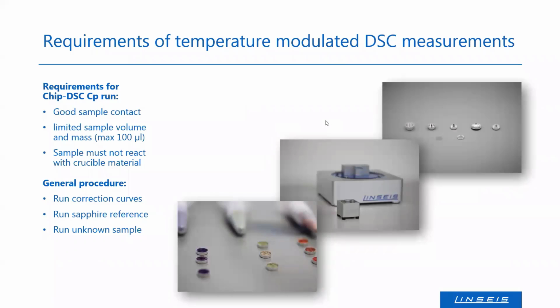So there are some things we need for these measurements. The most important thing is that the sample must be able to follow the temperature profile. Especially at lower temperatures near room temperature, or if you use a low temperature option near the lowest possible temperature, it could be hard to cool down because the temperature gradient is pretty small here. For this reason, the first period, and because it's not a complete period also the last period, of a measurement could be a bit strange. You should ignore them. By the way, in our software it's cut away automatically.